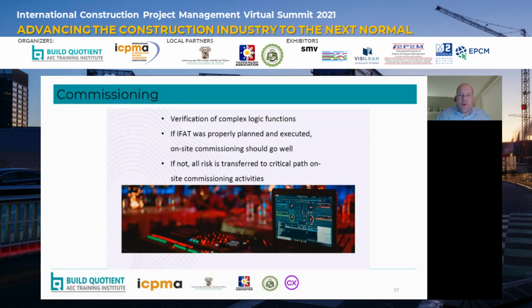So now that we've confirmed during pre-commissioning that everything is installed through loop checks, verification of installations, we can now start working with some of the complex logic functions with the real I/O from the end devices, and confirm that what we saw in IFAT is now functioning on site in real world conditions. Some of the variations that would have existed from IFAT is we didn't have all the end devices in place. We were simulating a lot of those devices, but now that we have those devices installed in the field, we can verify all the complex logic functions during commissioning.